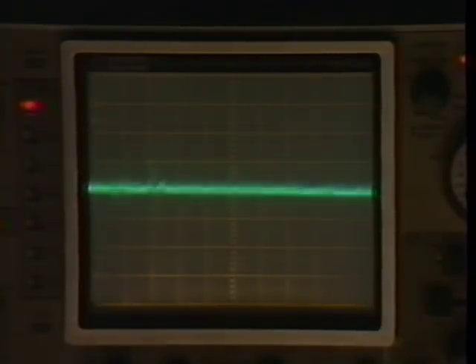Once the alignment looks correct, continue to the dynamic error amplifier adjustment. This alignment fine-tunes the VCO frequency to match the incoming data as closely as possible. Attach your test probe to the VCO control input. Your diagnostic will tell you what test point to use. Your scope will display a DC voltage of about 2 volts.